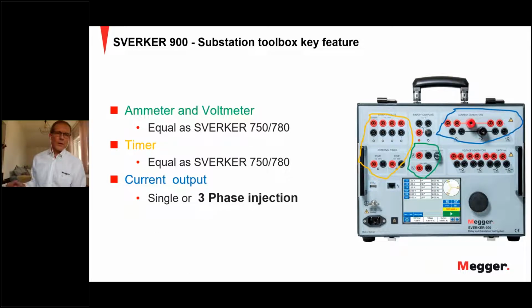And we also have the current output. But here is the biggest difference. Here you have the possibility to inject 3 currents to do 3-phase injection. But the very unique thing with the Sverker 900 is that we have jumpers, so it's very easy to make a connection and to run the Sverker 900 in single mode. And then you can inject higher current when you, for example, connect all the 3 currents in parallel.